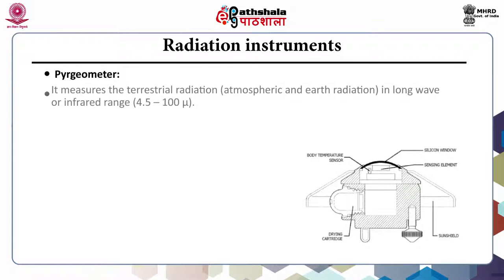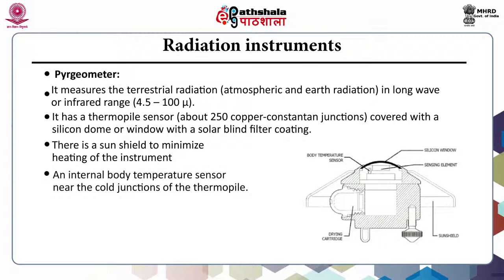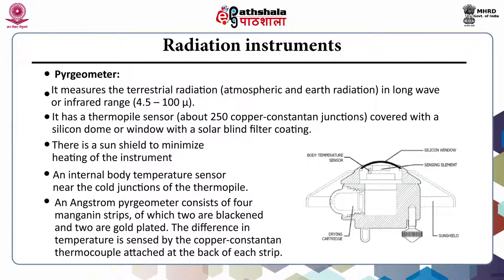Next comes the pyrgeometer. It measures terrestrial radiation — that is, atmosphere and earth radiation — in the long wave or infrared range, that is 4.5 to 100 microns. It has a thermopile sensor with about 250 copper-constantan junctions. This is covered with a silicon dome or window with a solar blind filter coating. There is a sun shield to minimize heating, and an internal body temperature sensor placed near the cold junction of the thermopile. In the Angstrom pyrgeometer, there are four manganin strips, of which two are blackened and two are gold plated.